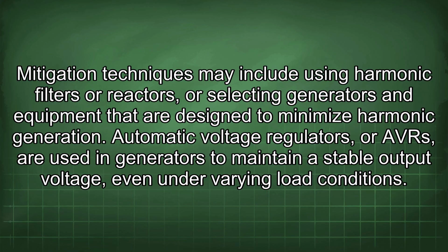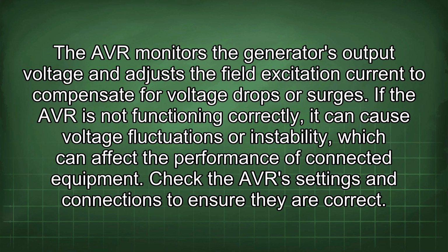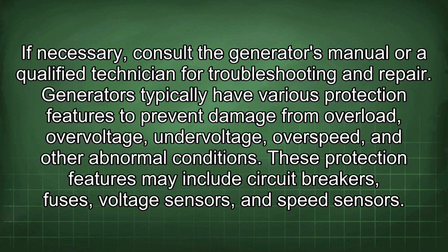harmonic generation. Automatic voltage regulators, or AVRs, are used in generators to maintain a stable output voltage, even under varying load conditions. The AVR monitors the generator's output voltage and adjusts the field excitation current to compensate for voltage drops or surges. If the AVR is not functioning correctly, it can cause voltage fluctuations or instability, which can affect the performance of connected equipment. Check the AVR settings and connections to ensure they are correct. If necessary, consult the generator's manual or qualified technician for troubleshooting and repair.